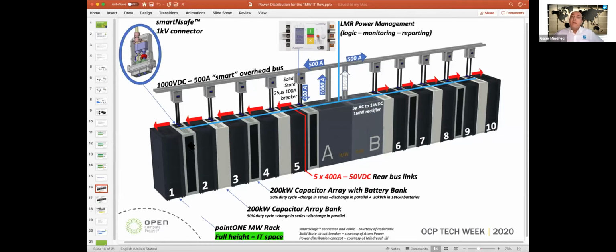That is probably one of the main challenges of such an architecture. It can be done. And what we show in this concept is a section utilizing only a capacitor array bank and a section utilizing a mixture between a capacitor array bank and a battery bank. And the idea is down converting 1000 volts DC to 50 volts DC. So if we have 100 amps at 1000 volts DC, the challenge really behind the rack will be to supply 5 bus links at 400 amps each, because that's a total of 2000 amps at 50 volts DC.